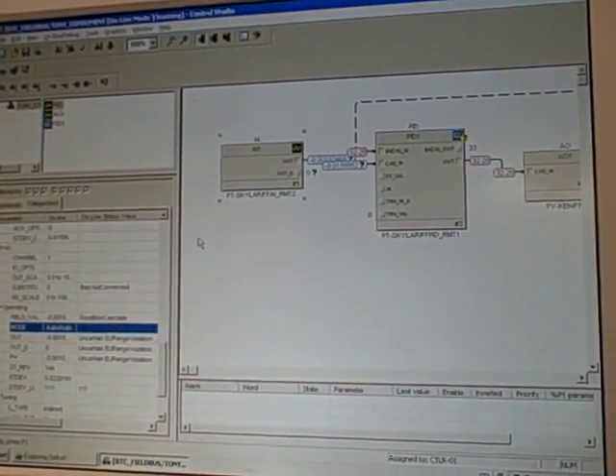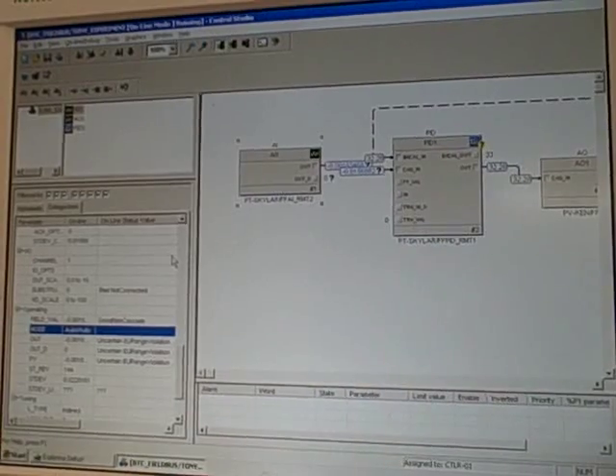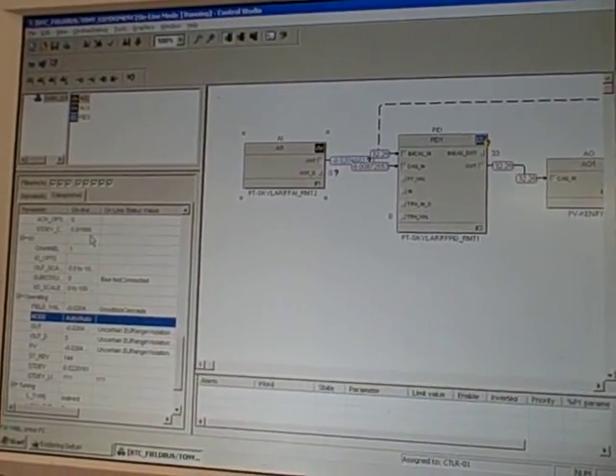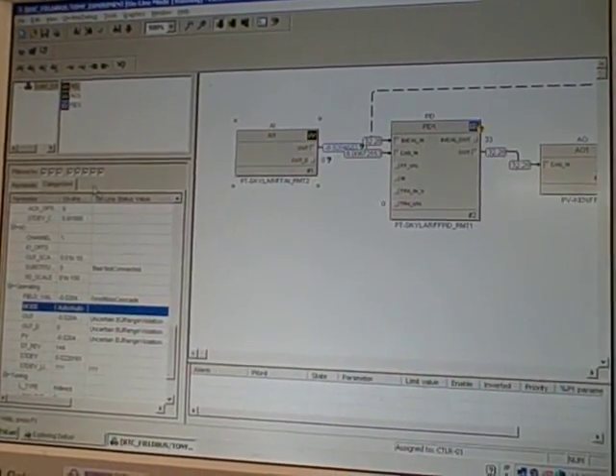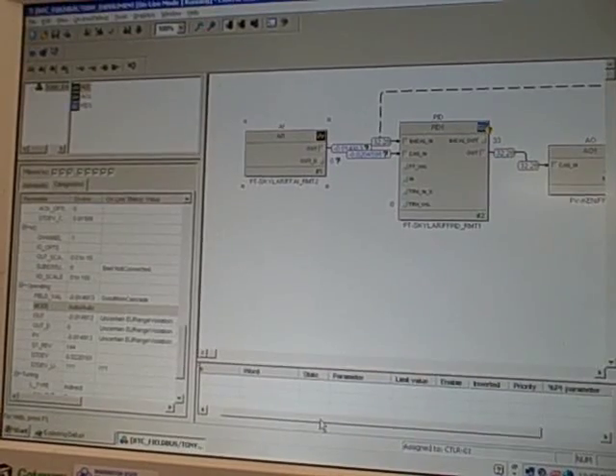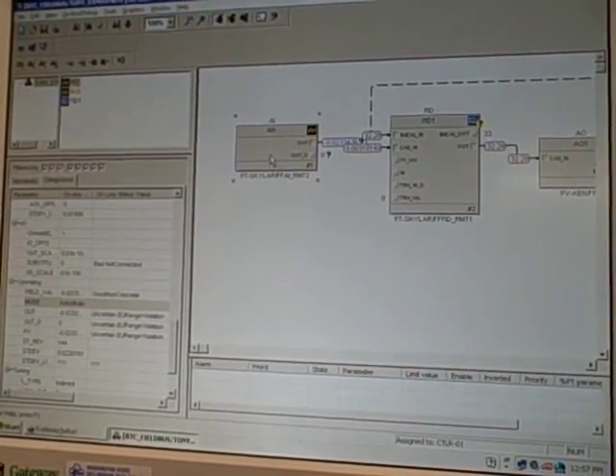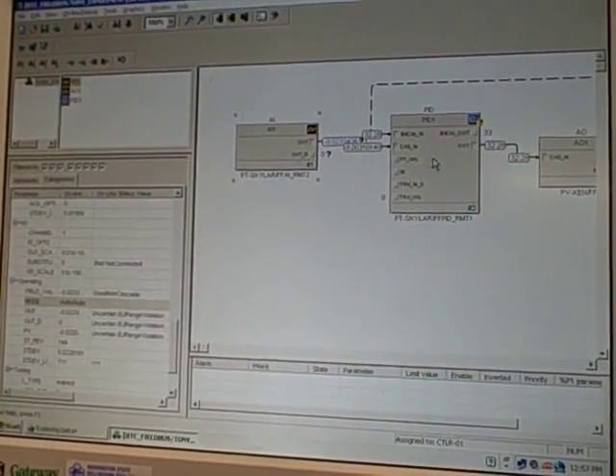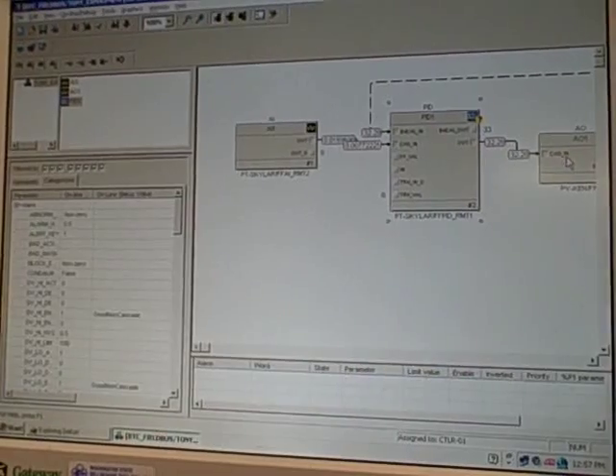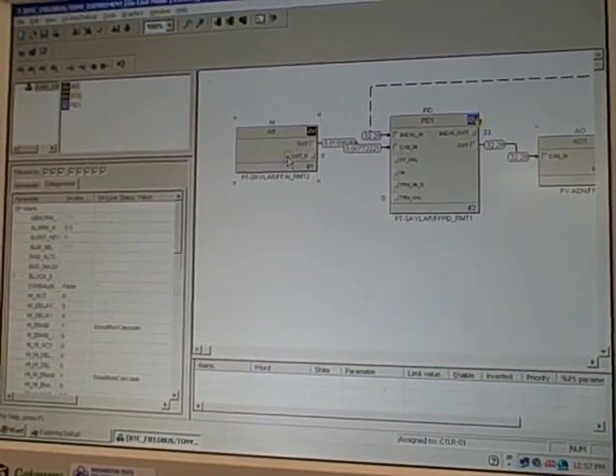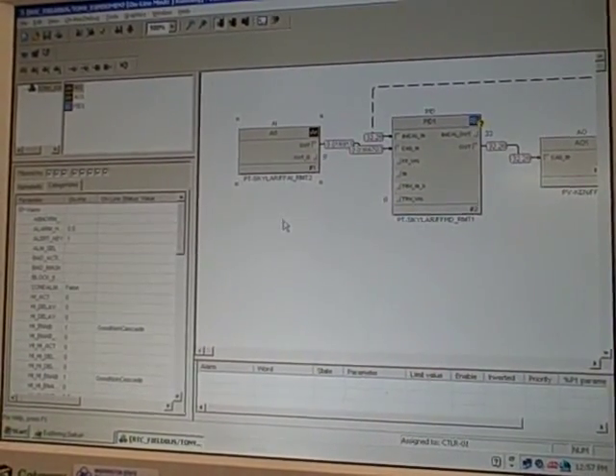So here we're looking at the function block screen of our DeltaV DCS system. In this case, we're looking at a fieldbus loop. So right here, you see three function blocks: analog input, PID, and output. And these are actually Foundation Fieldbus instruments.